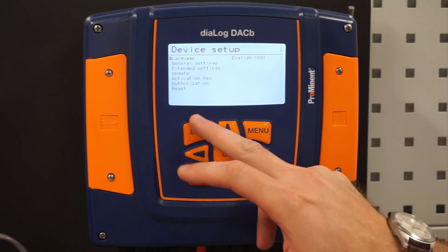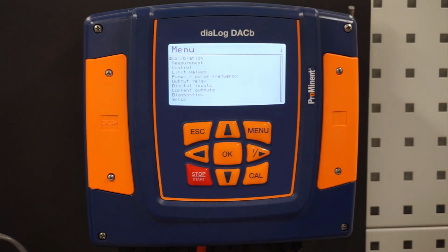At this point, we've gone through all the menus, we've made sure everything's programmed correctly. If we're doing pumps, we have those set up. Our limits are either turned off or set where we need them to be. We've had water running past our sensors, so the electrolyte is charged. If it's a free chlorine sensor, we've let it burn in for maybe 1 to 2 hours, and we're ready to do our initial calibration. So that would be our next step.